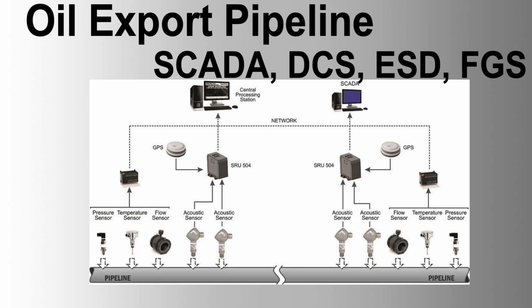4. Fire and gas detection system, F&G. Example, Det-Tronics Eagle Quantum Premier. Hardware specifications. Control panels, Det-Tronics EQP control panels with SIL 2/3 certification. Detectors, infrared and catalytic bead gas detectors, flame detectors, and smoke detectors. Networking, redundant Ethernet or fiber optic networks for robust communication. Power supplies, redundant power supplies with battery backup for continuous operation.